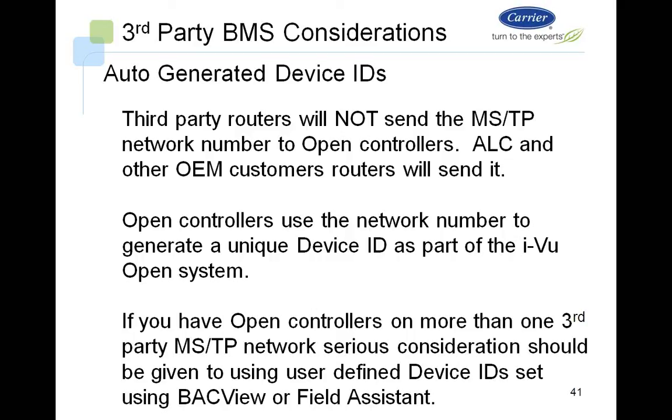But if you're using an Alerton, or if you've got controllers that reside under an Alerton MSTP router or a Cimetrics or Contemporary Controls MSTP router, the router will not send the MSTP network number to the open controllers.